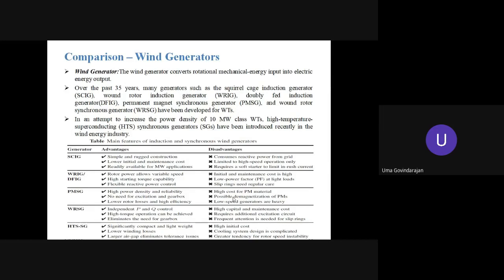And the fourth one, the wound rotor synchronous generator. It is possible to have independent real and reactive power control. High torque operation can be achieved, and it also eliminates the need for a gearbox. But similar to the PMSG, it has a high capital and maintenance cost, requires an additional excitation circuit, and frequent attention is needed for the slip rings.